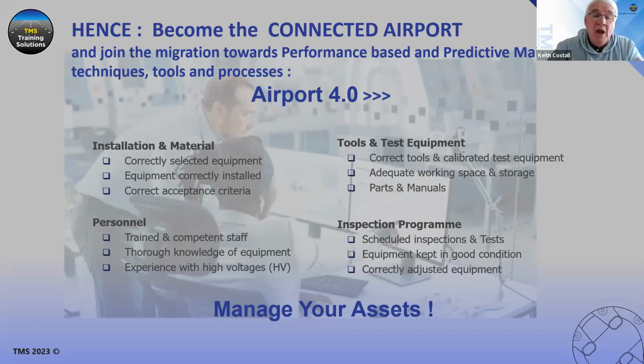So I put these four areas that we look at, whether we do an inspection, an audit, or whether we just look at it from a management perspective in terms of maintenance. We look at the installation of the material, what we've got in the field. Have we got the correct equipment for the function, be it runway, taxiway, or apron lighting? Has it been correctly installed and set to work? And the acceptance criteria—was this acceptance criteria there?